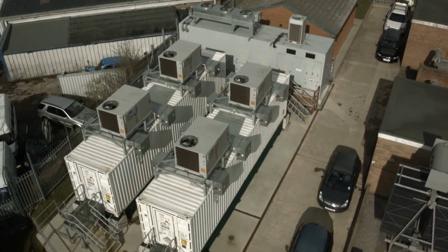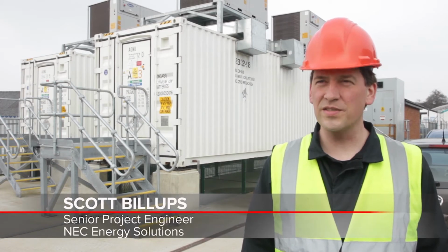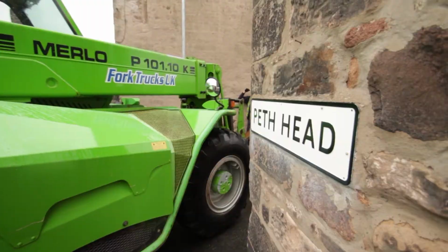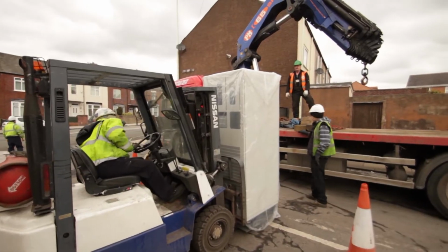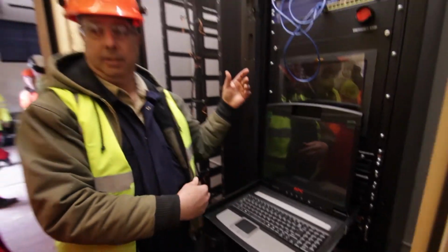Battery systems are a new technology, and this is the first project of its kind in the UK. Northern Power Grid selected these 6 sites because taken together as a whole, they represent about 80% of all of the UK's electrical grid. Each site presented its own problems, mostly with physical constraints, because we were trying to get the batteries located directly next to the loads in the small neighborhood. The primary reason for having 6 different batteries at various scales, some being large, some being medium and some being small, is that we can fit them across the entire range of our distribution network.